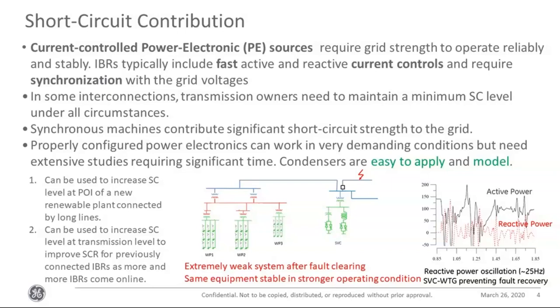And some transmission owners might be required by regulations to maintain a minimum short circuit level. Even under N-1, N-2 conditions, you might be required to maintain a minimum SCR level. And that's where synchronous condensers are found to be helpful. Now, this might be at a new plant that is being connected, so you might want to increase the short circuit strength at the point of interconnection with the help of a synchronous condenser. Or, as you already have more and more IBRs at the transmission level, the short circuit strength is reduced, so the synchronous condenser might also be connected at the transmission level.